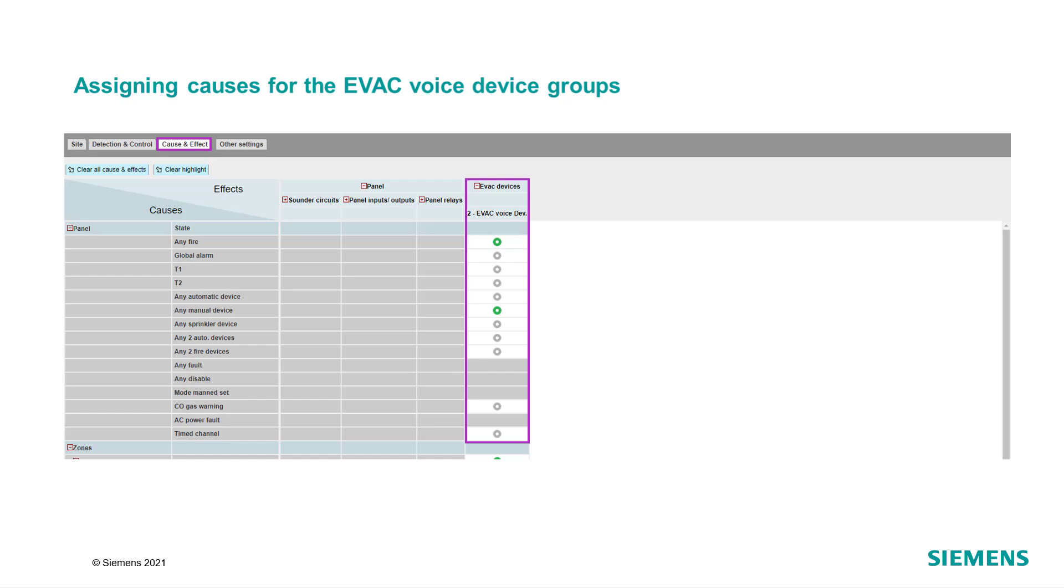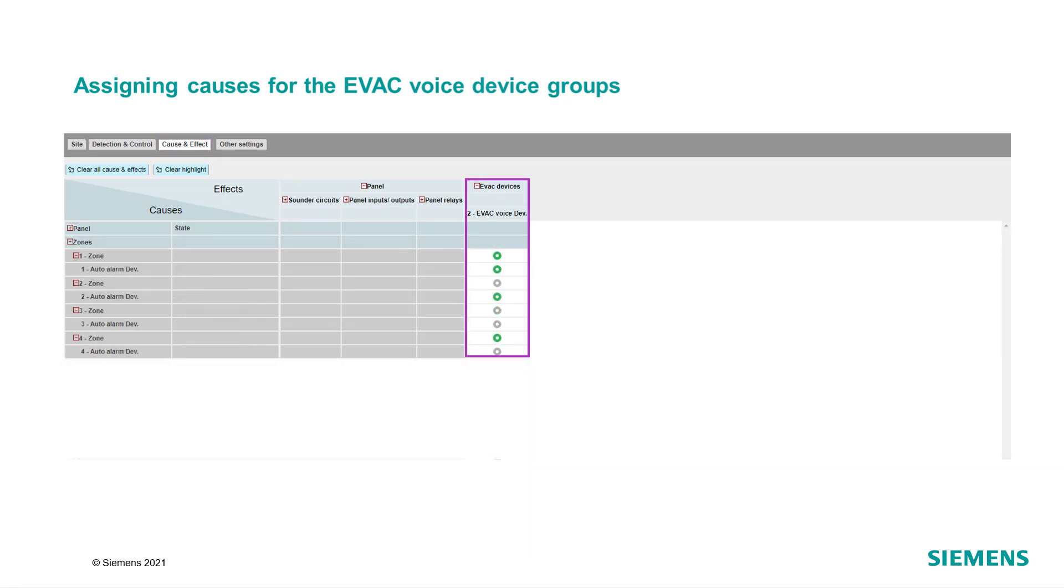In order to configure the cause for the voice activation, go to the cause and effect tab and expand the Evac devices. Activate each event from the panel that should activate the Evac voice device group. Close the panel tab or scroll down to define single zones or devices to be assigned as a cause to each Evac voice device group.